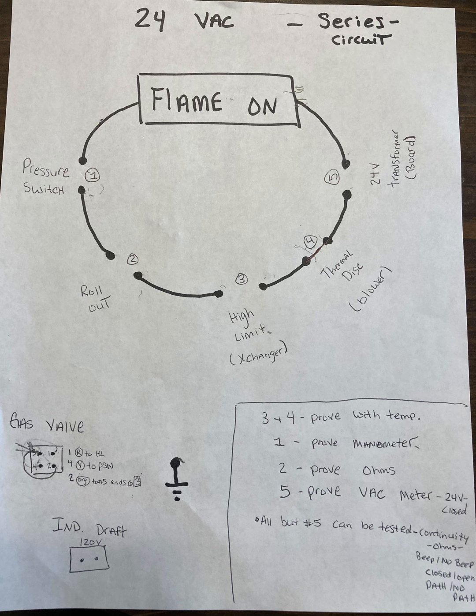Looking at the picture above us, I have a typical setup for an 80% furnace. These are the safeties that are in that control circuit, and this is how it works. In a normal furnace situation, my flame is on and everything's running great. I can use my hopscotching method. I can plant one of my leads down here at the ground connection, any good ground that I can find, and use my free hand with the other side of my lead to touch one of these spades. Every dot on my map up here is a spade coming in and out of one of these safety switches.